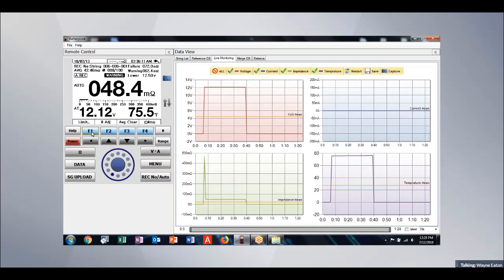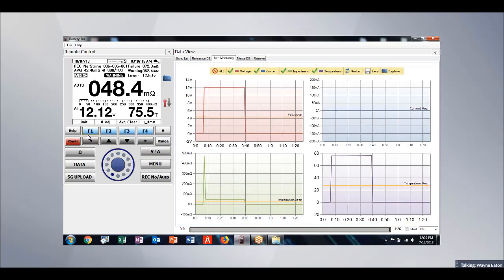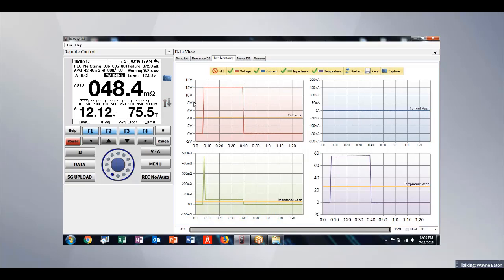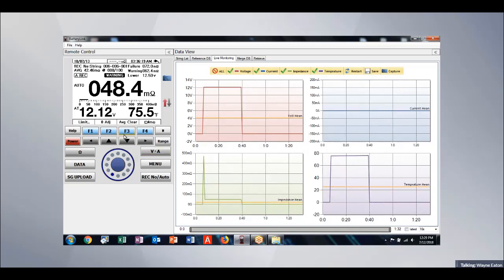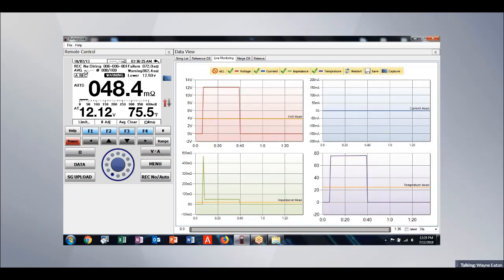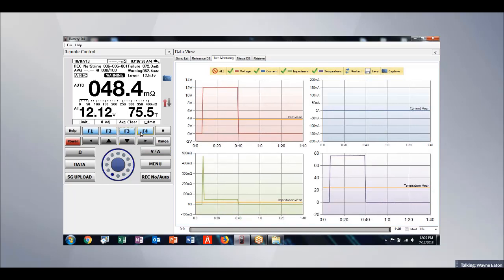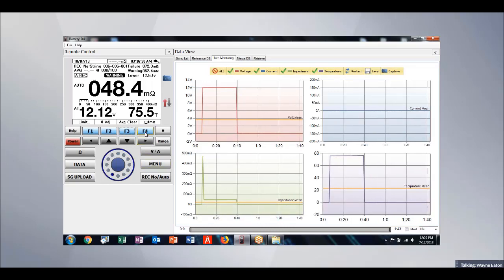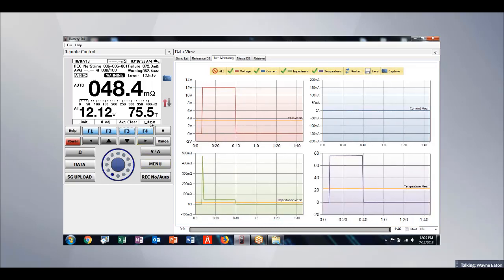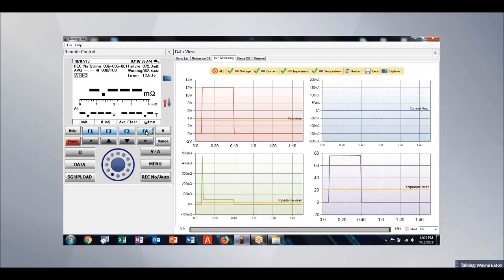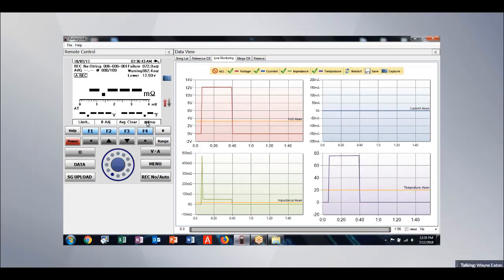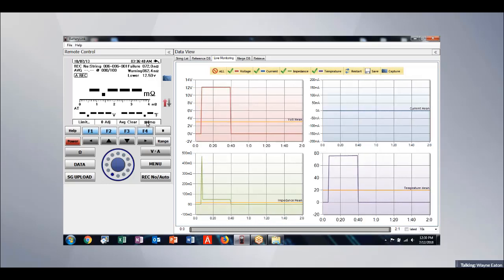All of our screens have all the controls right here on the key panel. So when I'm connected to the software, anything I do in the software actually has the same effect as if I did it on the handheld unit itself. Some of the little tricks, this F4 key, 4 milliohm scale. If I'm doing 2-volt individual cells, I want to put it into that milliohm range so that I don't get overload readings on the scaling of the unit. Just something to remember.